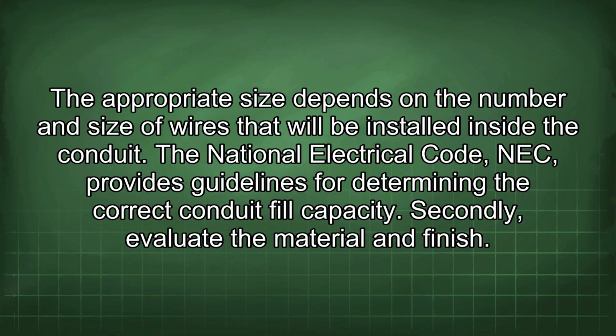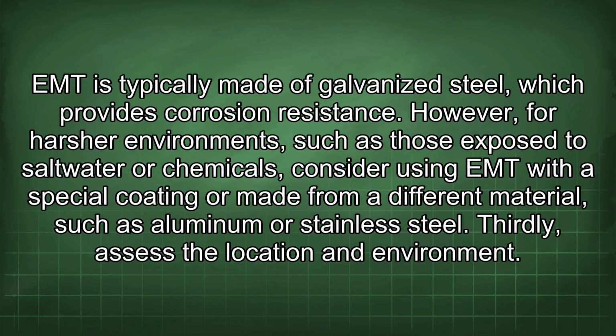Secondly, evaluate the material and finish. EMT is typically made of galvanized steel, which provides corrosion resistance. However, for harsher environments, such as those exposed to saltwater or chemicals, consider using EMT with a special coating or made from a different material, such as aluminum or stainless steel. Thirdly, assess the location and environment.